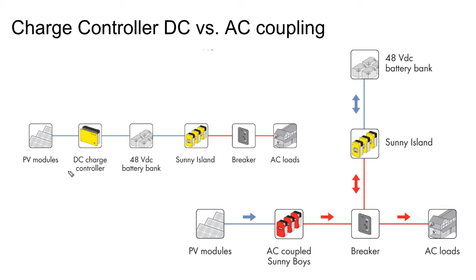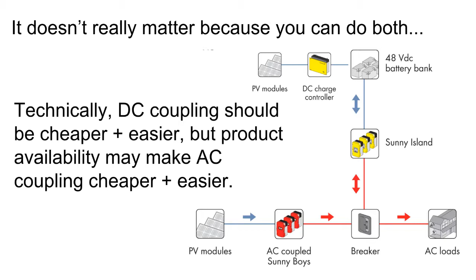All the disadvantages of AC coupling instead of DC coupling are pretty much resolved by that backup generator turning on for 15 minutes and waking up the system, getting the solar array back up to where it should be, or turning on before then so the batteries don't run out of juice. You can program the battery inverter to cut off before it runs out of juice, so it has enough reserve power to start the solar inverter the next morning once the sun comes up. So let's just leave the AC versus DC coupling discussion aside, because the pros and cons are too close together to merit more time in this program.